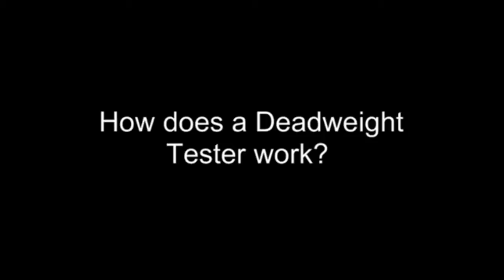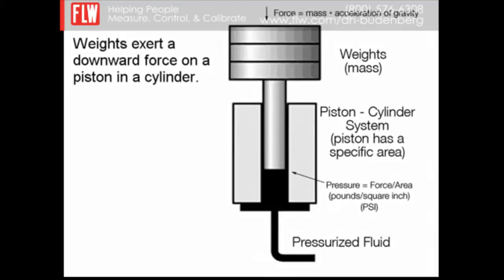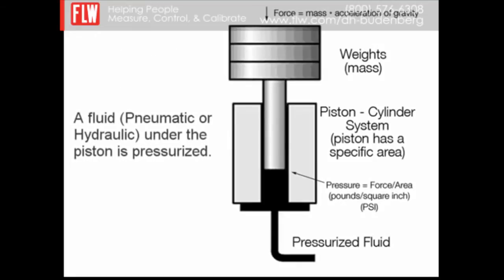How does a dead weight tester work? A dead weight tester generates a force over a specific area. Weights are placed on a piston and exert a force on a fluid in a cylinder. The fluid is pressurized under the piston.